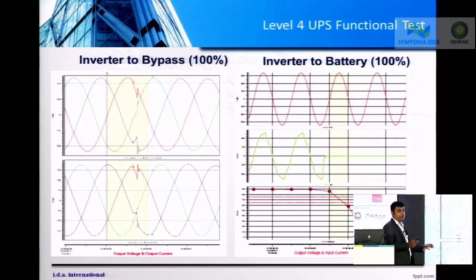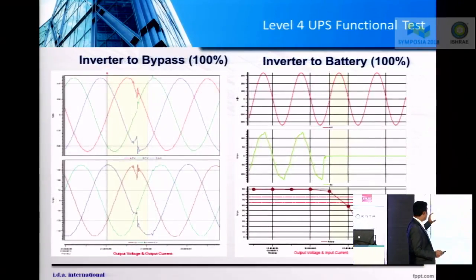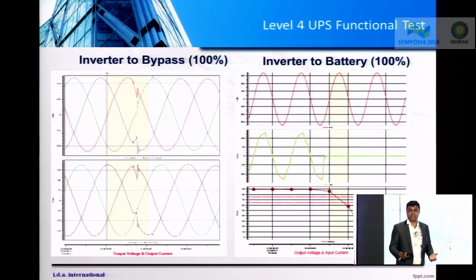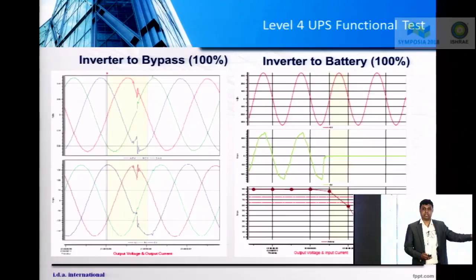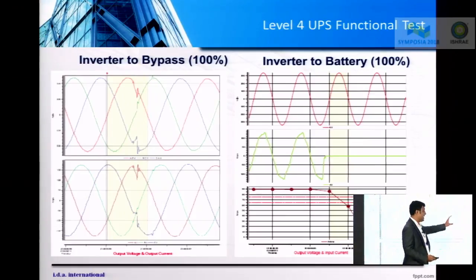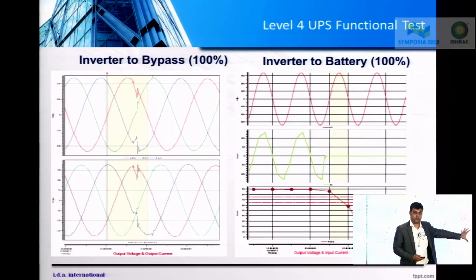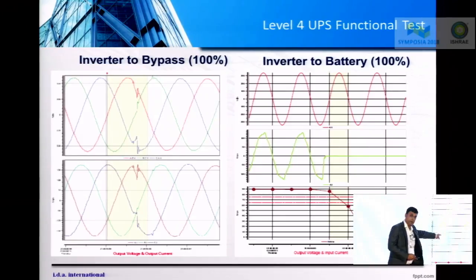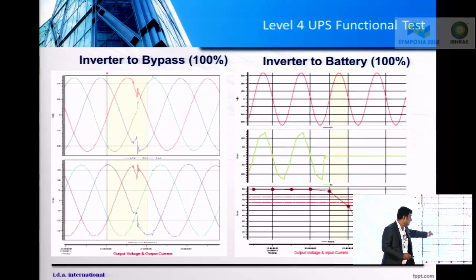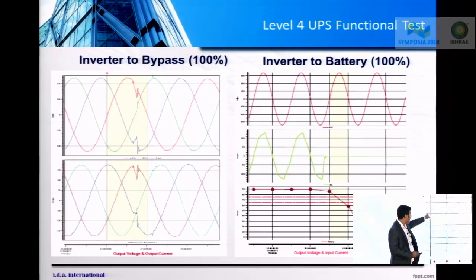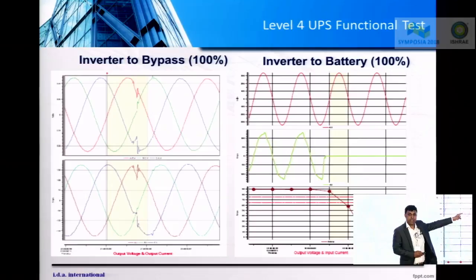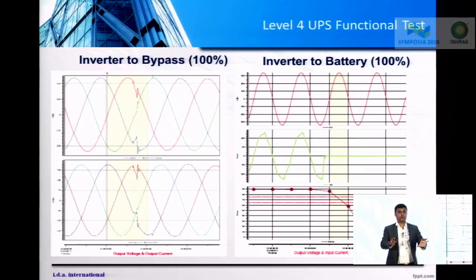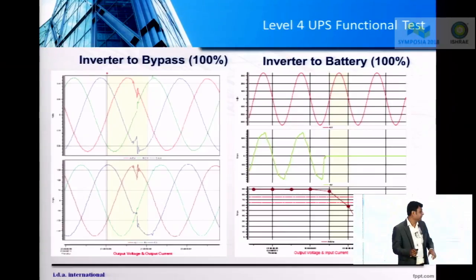Let's take example of a transfer test. When there is a mains failure, when the input supply to the UPS fails, it jumps to its battery, right? During this transfer, it is very important to capture a waveform that shows that the input current was pretty good. Suddenly the power fails, the input power supply was dead, but there is absolutely no impact on the output supply. The output supply was intact, there is no break, which means the performance of UPS is great.